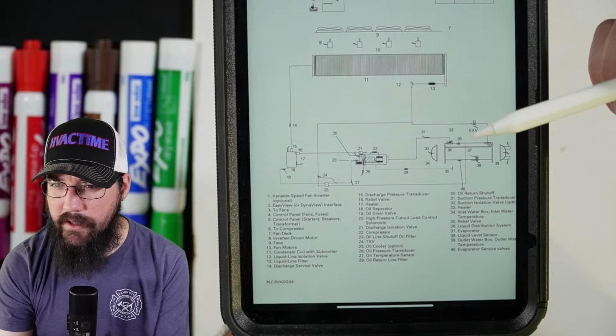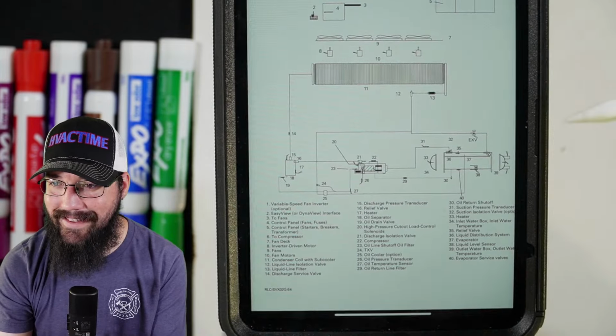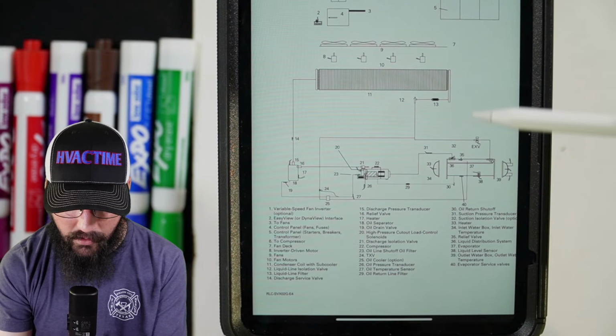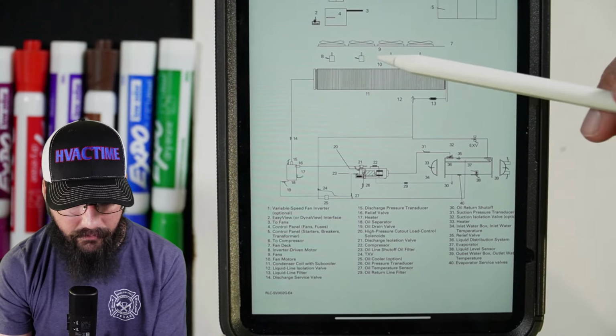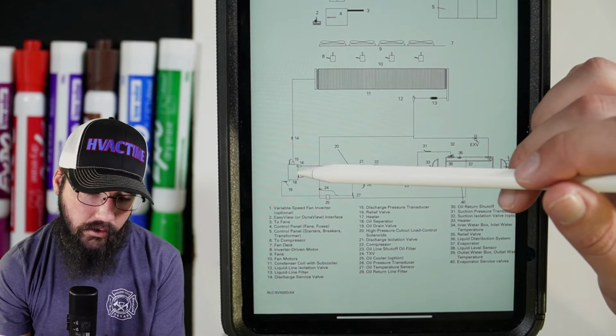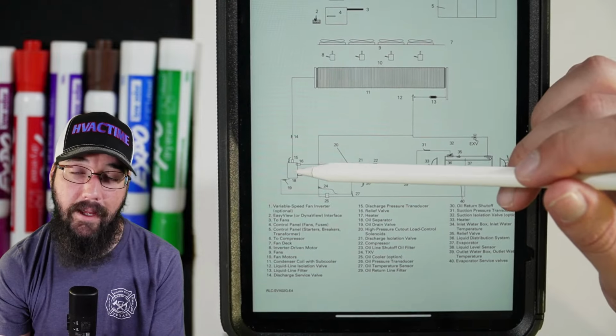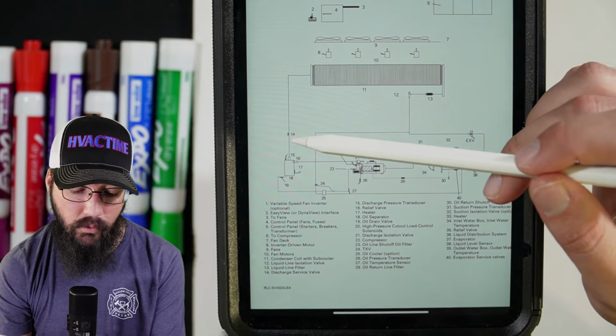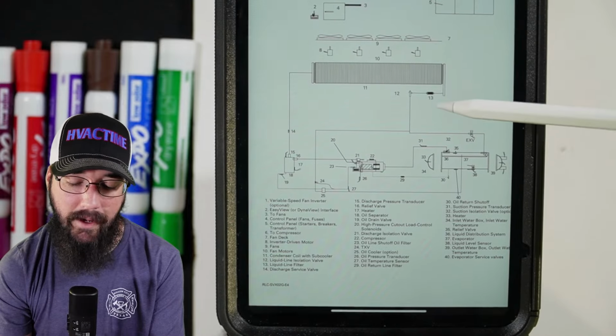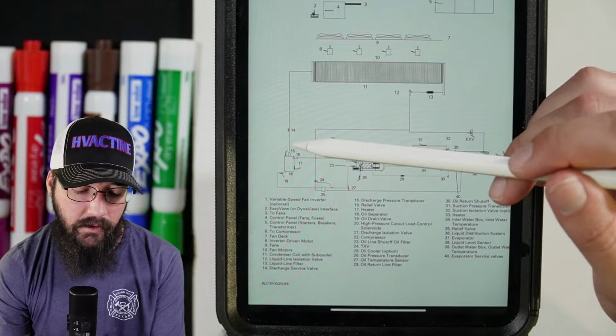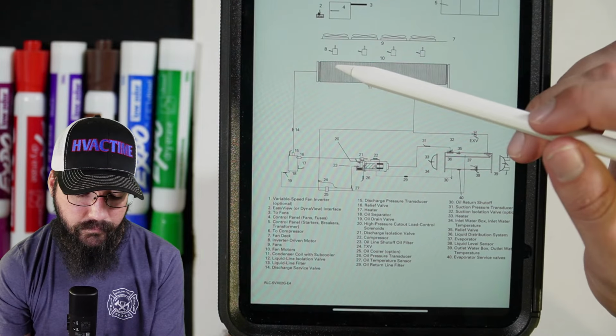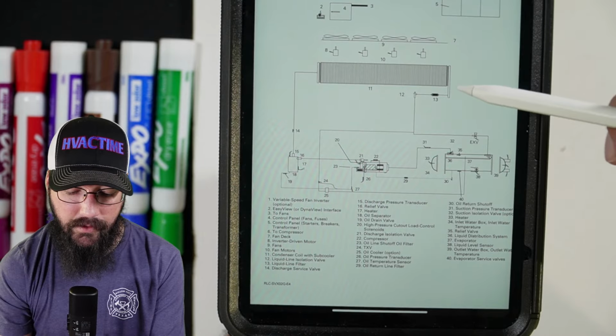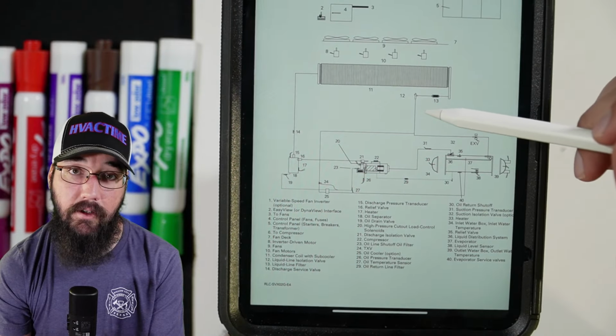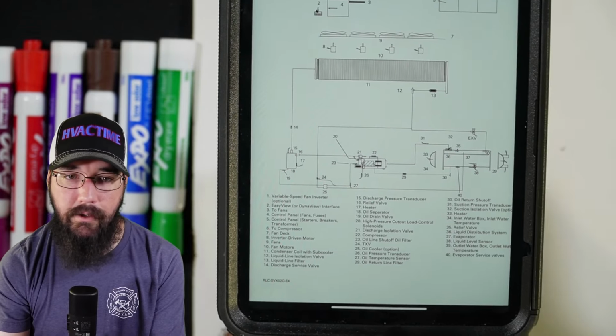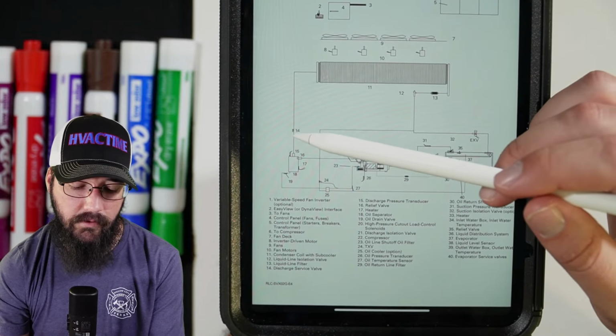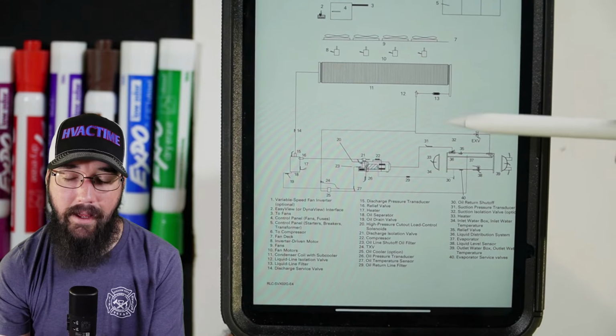Now the question is, how does oil enter the evaporator and then return to the compressor? These oil separators don't remove all of the oil from the refrigerant vapor. It removes a lot of it, but not all of it. It is not a pure refrigerant that leaves this and heads back to the condenser to recirculate. So the little bit of oil that does make it up does process through the condenser, and then as it goes through the condenser, it drains back out and starts back through our liquid line. Same way oil flows through any refrigerant circuit. Whether we have a separator or not, some oil does make it up into the condenser, and we do have that drain back into our evaporator.